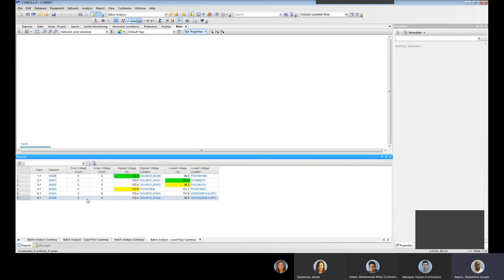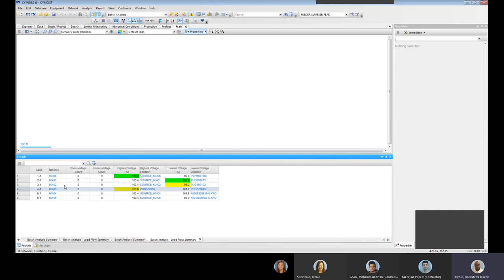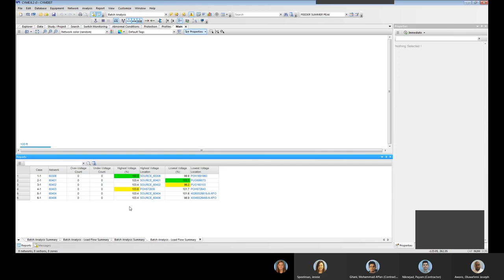You can export this to Excel and you can sort these as well. So we are interested in just the low voltage. Zero low voltage count. This seems to be really good feeders. And even the low voltage, the lowest we could see here is 96.2, which is still within range. So we don't want to care much about these feeders. This looks like perfect feeders. Like 96.2 is the lowest voltage, and this is the location of the lowest voltage. You can actually click this and go to the lowest location or investigate further on the feeder. And that's all. That's all about batch analysis.